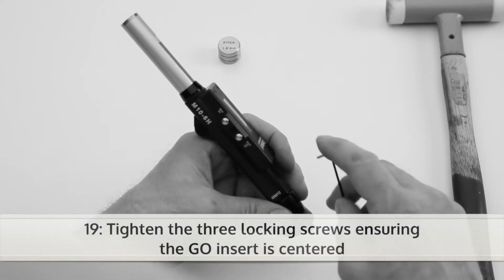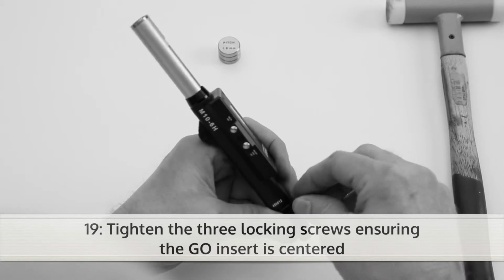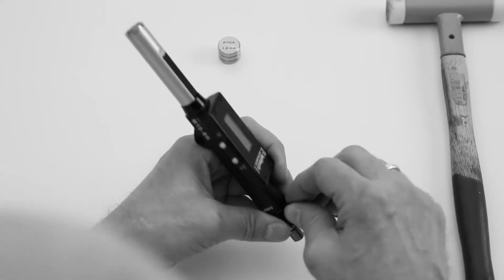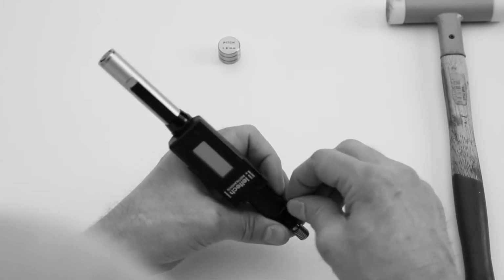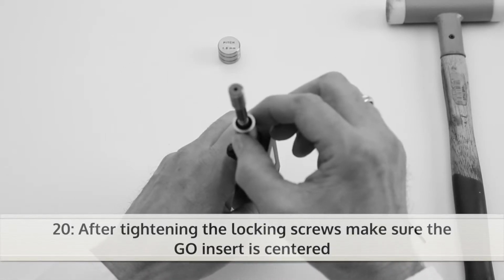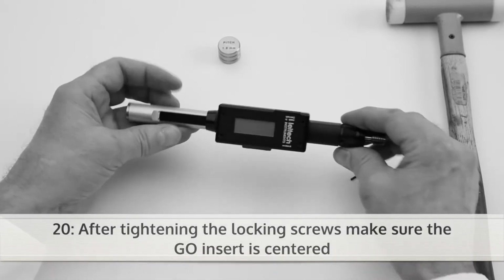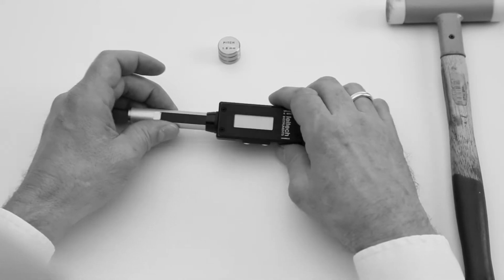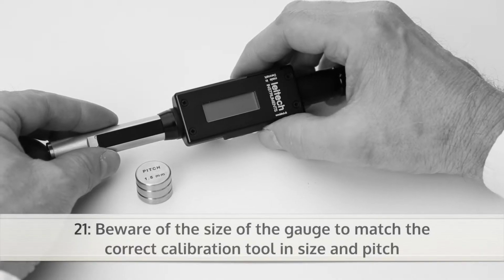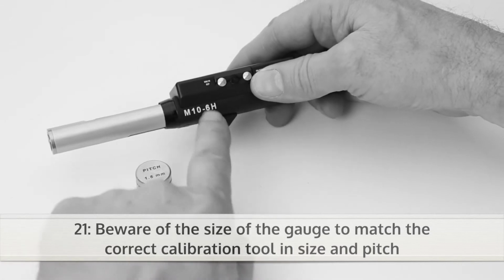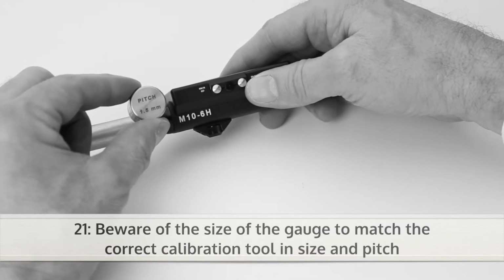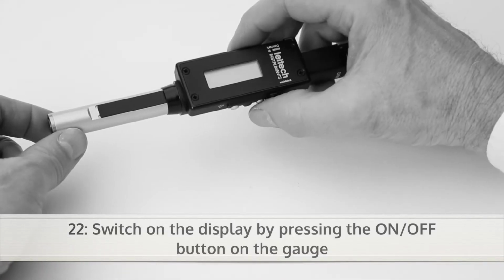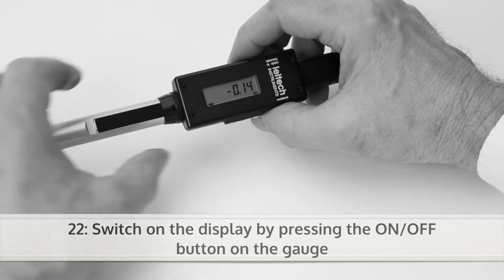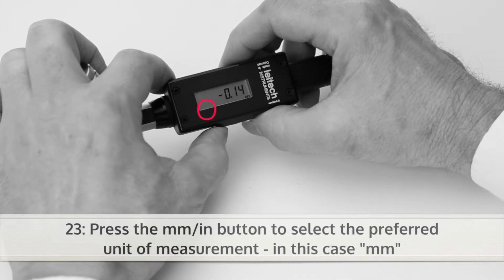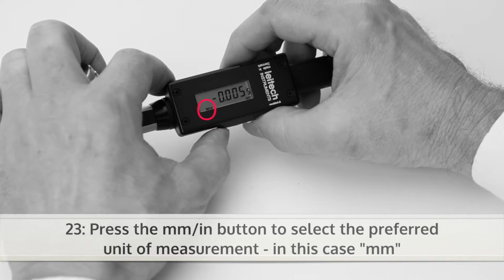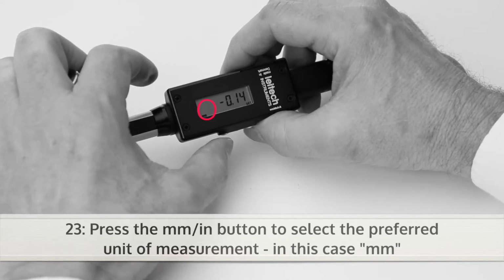Now you can tighten the 3 locking screws, ensuring the go insert is centered. After tightening the locking screws, make sure the go insert is centered. Be certain the size of the gauge is matching the calibration tool in size and pitch. Now switch on the display by pressing the on/off button on the gauge. Press the mm/inch button to select the preferred unit of measurement, in this case millimeters.